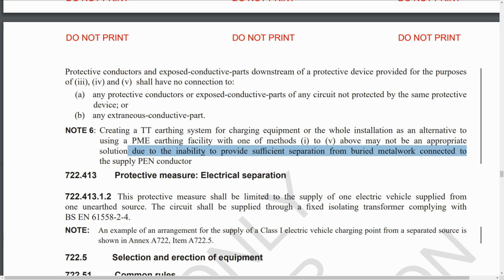And the same applies to putting it near electric cables in the ground, because again, it's too close to existing electrical equipment. So water pipes, gas pipes, incoming supply cables, and pretty much any other electrical or metal items that are in the ground that are connected to the installation in some way. Now, how far away it has to be does seem to vary. Generally the rule was that the length of the electrode multiplied by 2 is the absolute minimum distance between it and something else. So if you had, say, a 1 metre depth electrode, you need it at least 2 metres away from any other items within the ground.